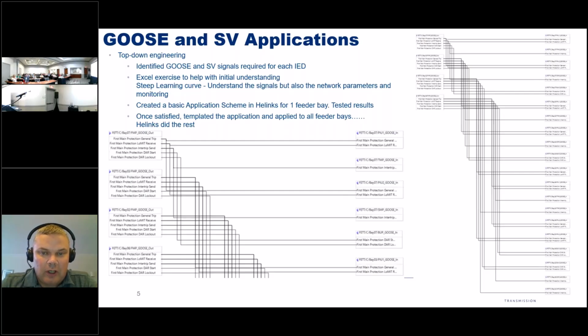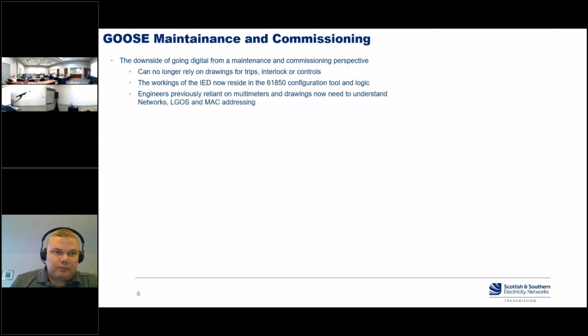difficult to follow and diagnose as well when you're new to this and you're looking at Wireshark publishers or Wireshark packet streams. It's not really a practical way to find out if your GOOSE is working healthy. So what did we do to have a look at that?